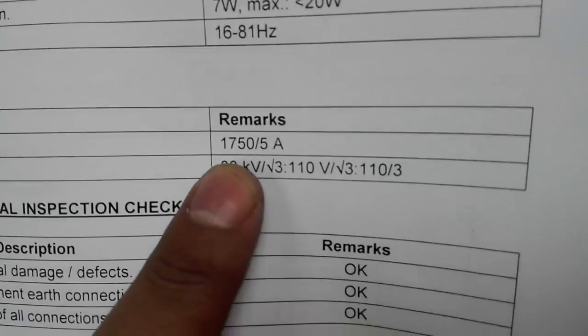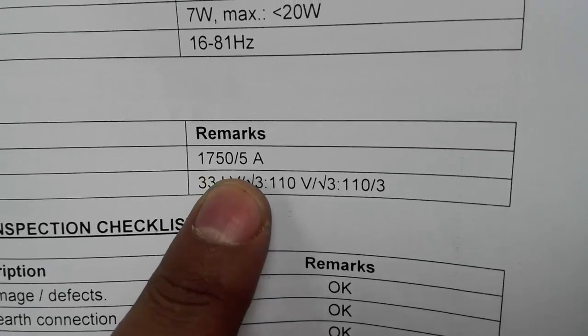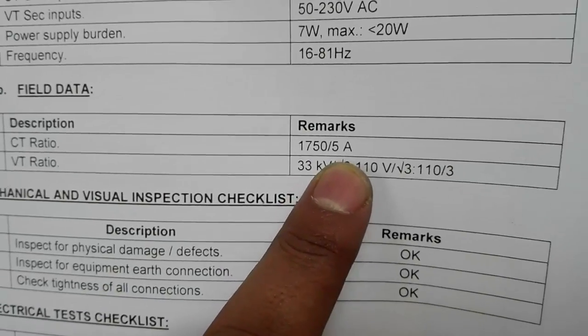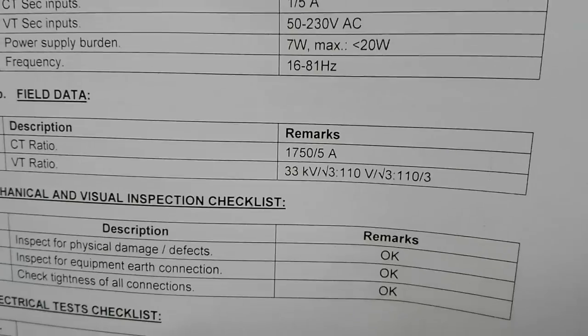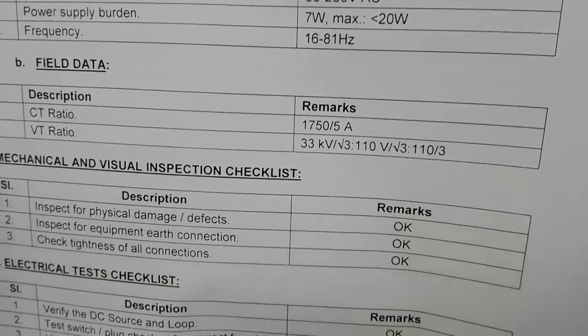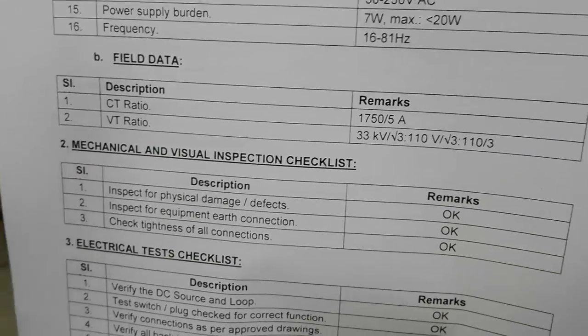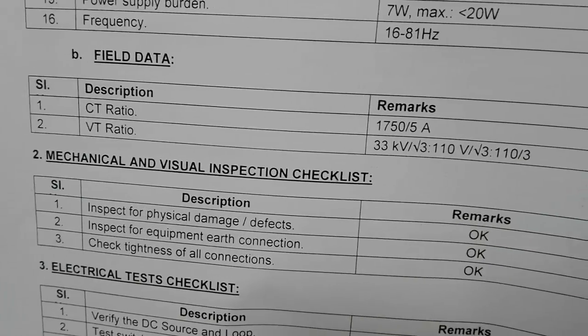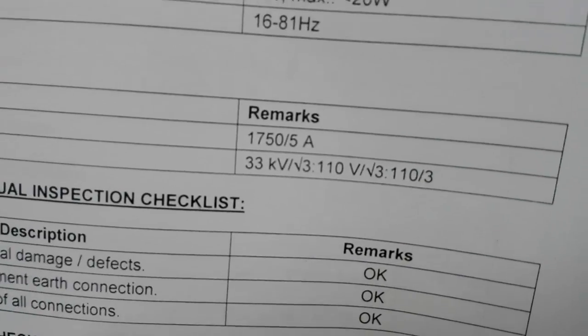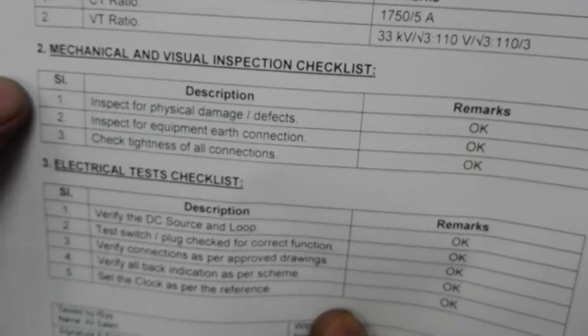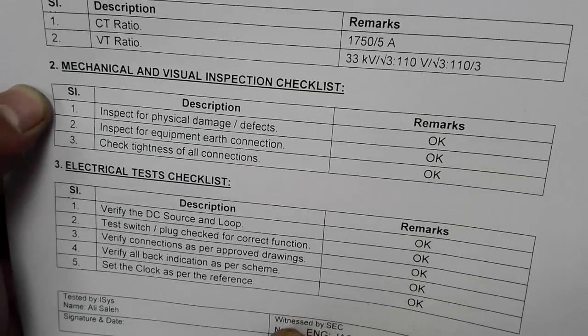CT ratio here is 1750 divided over 5 amperes. Primary is 1750, secondary side 5 amperes. It will read like this. VT ratio 33 kV and 110. Okay. Mechanical and visual inspection checklist.